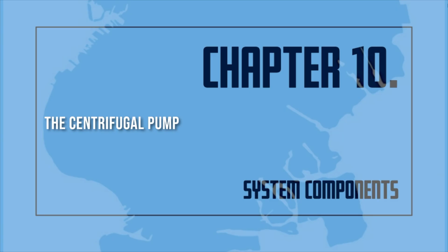Most centrifugal pumps have a single impeller and are therefore commonly called single-stage fire pumps. The vertical turbine pump. A vertical turbine pump is really a modified centrifugal pump that has the capability to draw water from streams, ponds, and wells. Unlike the standard centrifugal pump, the vertical turbine pump does not need the suction supply to be under pressure for it to operate. Instead, it draws the water into the pump by suction. When it reaches the rotating impellers, the water pressure is increased and then forcefully discharged into the fire protection system.